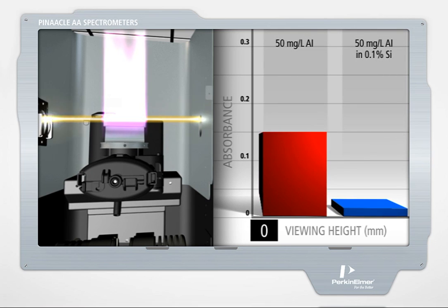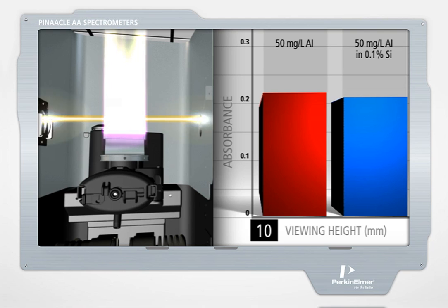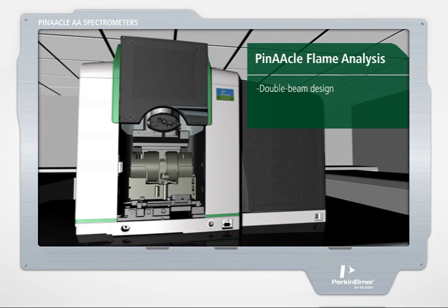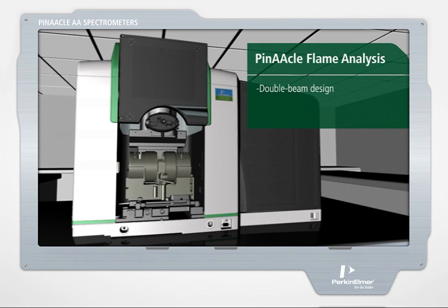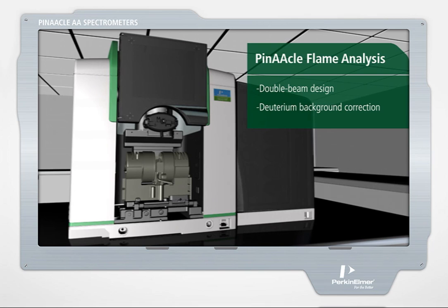Note the change in absorbance of both aluminum and aluminum in 0.1% silicon, as the viewing height is raised from 0 to 5, 10, 20, and 25 millimeters. PinAAcle's flame mode features a true double-beam design for fast startup and exceptional long-term stability without recalibrations, and deuterium background correction ensures maximum sensitivity and accuracy over a wide wavelength range.